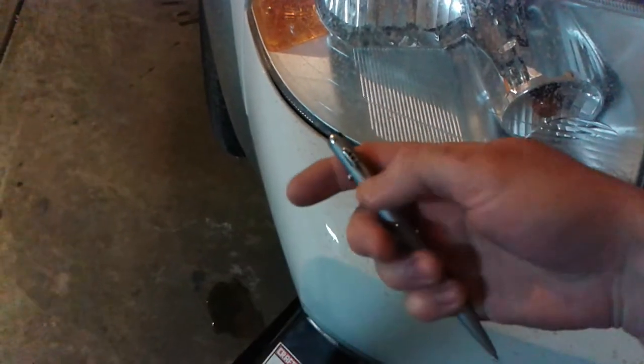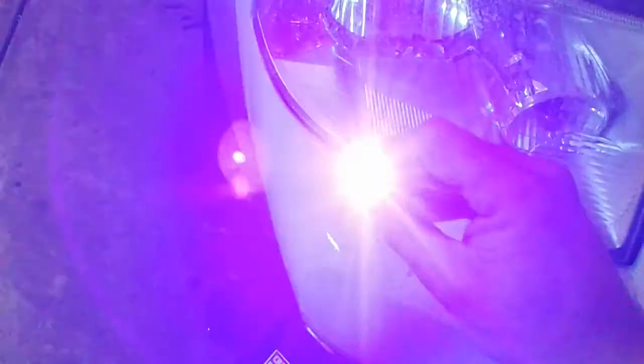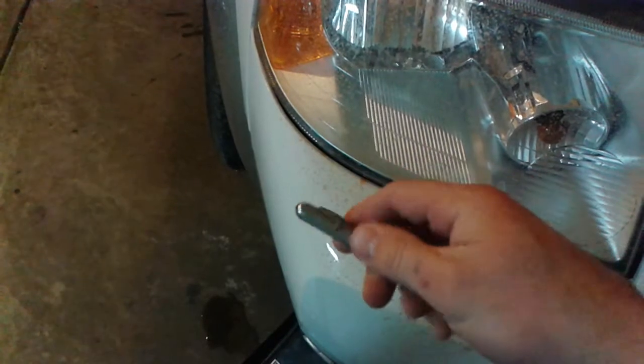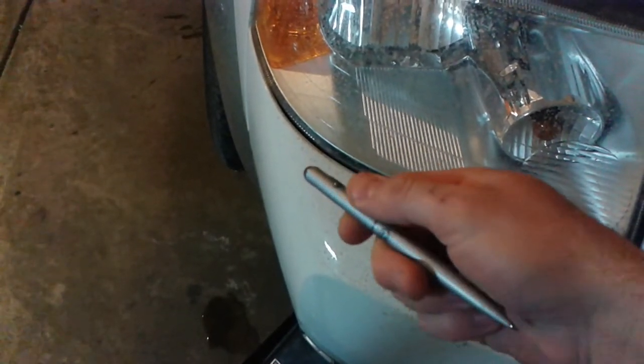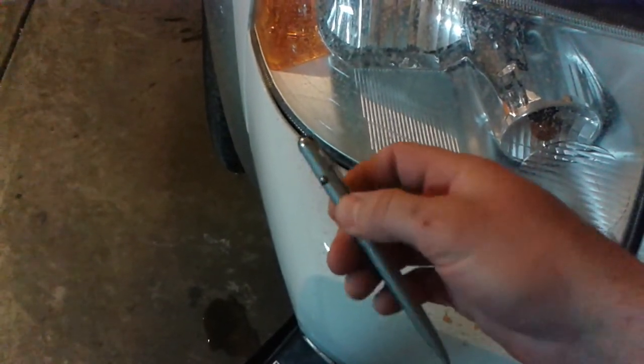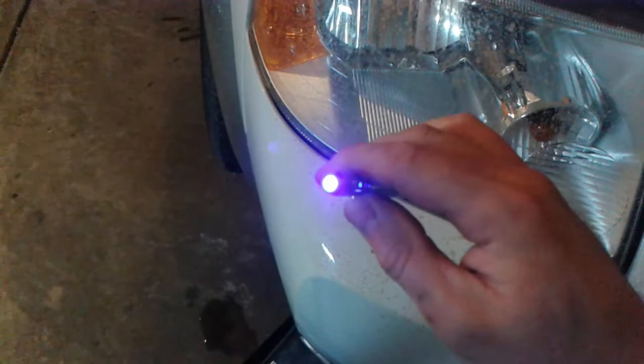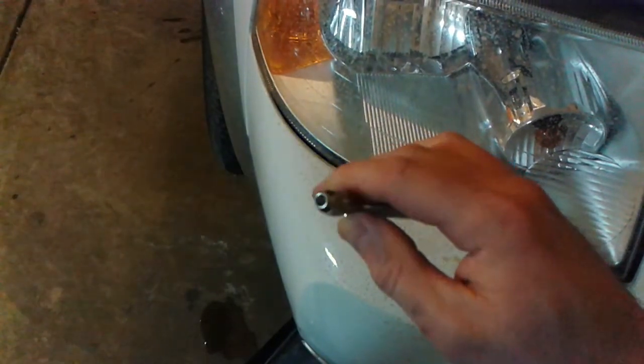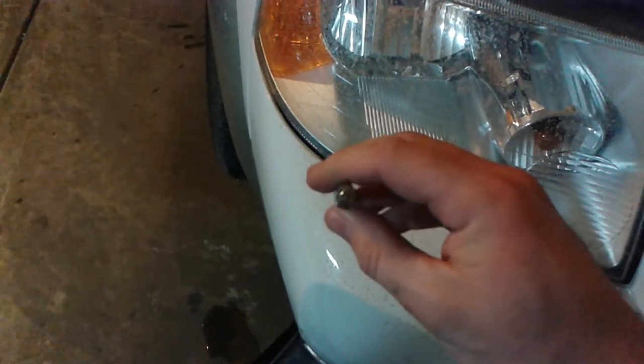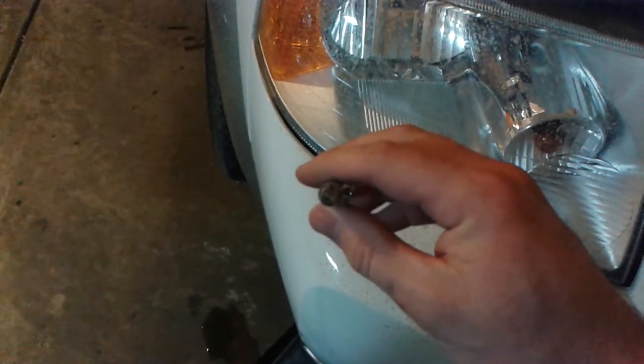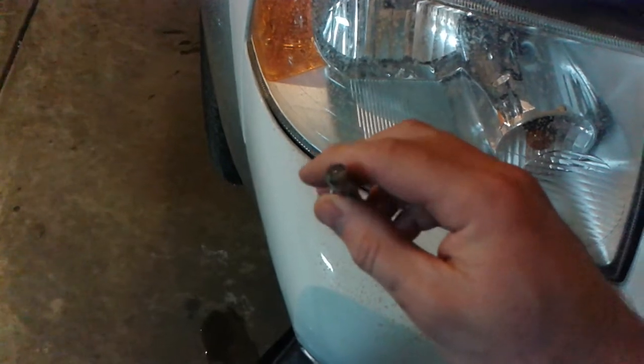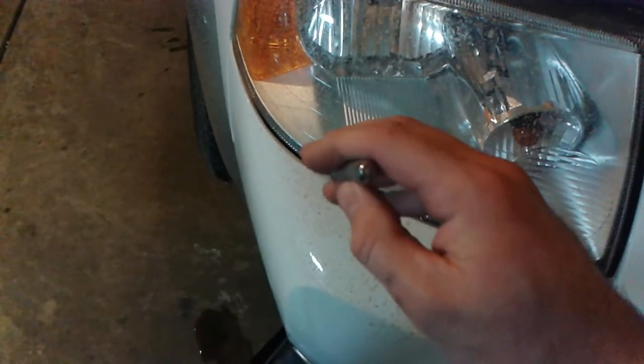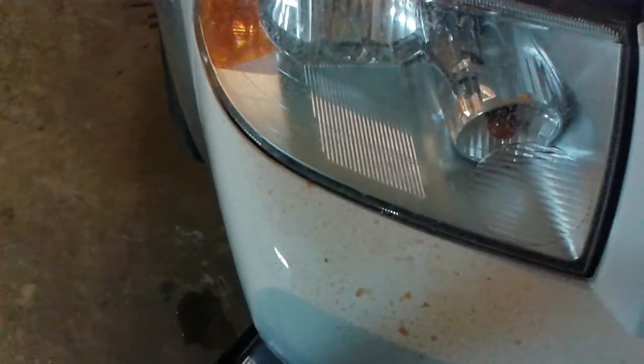I have an ultraviolet blacklight pen that I got from an air conditioning leak and dye recharging system. It's going to come in handy because the oil will turn bright orange where the dye is. So let's find out if I can pinpoint the leak.